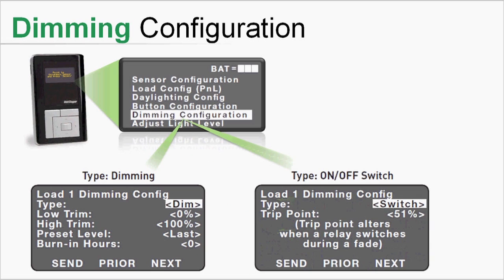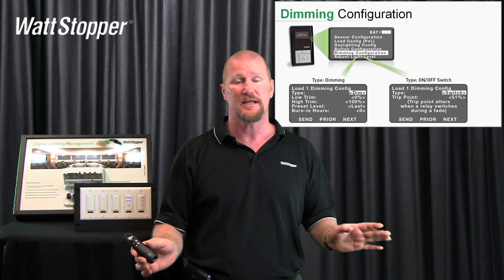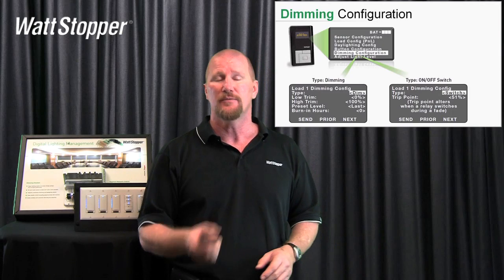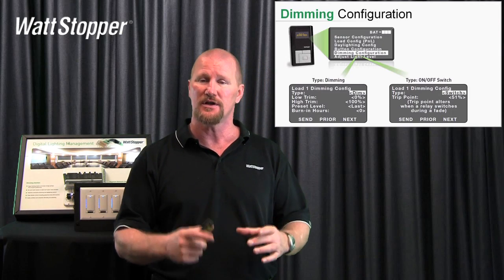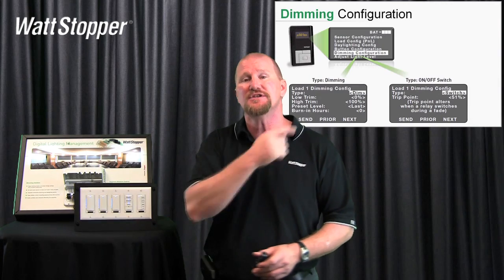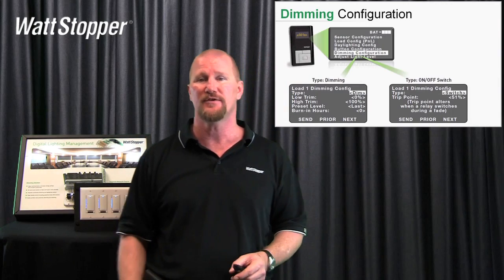Now, if your load type is a switched load, or if you change load type from dim to switch, it'll present this next screen. This screen just says: now I'm a switched load, and as a switched load my trip point is 51%. Remember we talked about trip point — so if I'm trying to ramp up or down a switched load, at 51% on the way up I'll turn on, and anything below 51 I'll turn off. This is where you change it. You don't have to change it — it works just great out of the box. But it is important if you have a switched load that you're going to run off one of these dimming room controllers to change it to a switched load so that the behavior is what you expect.